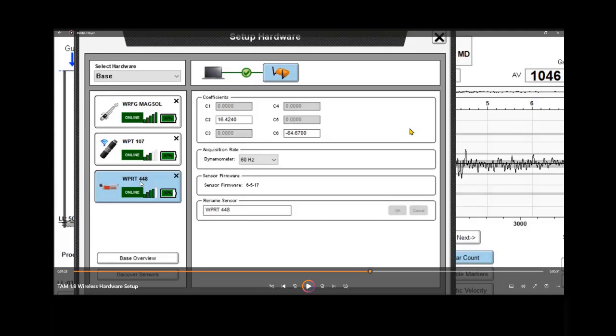The particular sensor displayed at this point is a WPRT, or wireless polished rod transducer, which is used in the acquisition of dynamometer data. This particular sensor only requires a C2 and a C6 coefficient. The information is automatically pulled into TAM from the board. If you have wired equipment, when you set up a brand new sensor, you need to manually enter the coefficients as printed on the transducer or as printed on the WPRT. Whatever sensor you have, you need to enter and save those coefficients as you build out the individual sensors.